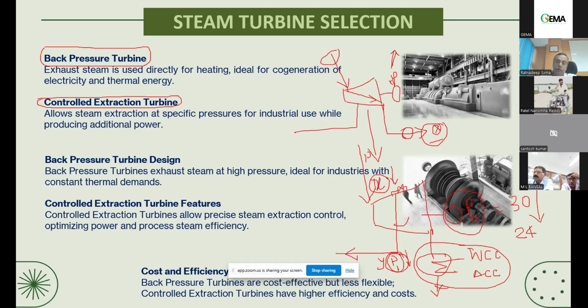You can have a control extraction turbine from a back pressure turbine also. So if you have a two pressure system, for example using 6.5 kg pressure for distillation - some technology allows that, particularly European technology where distillation is at 6.5 kg instead of 3.5 kg - and you can have a 3.5 kg pressure for your process steam.